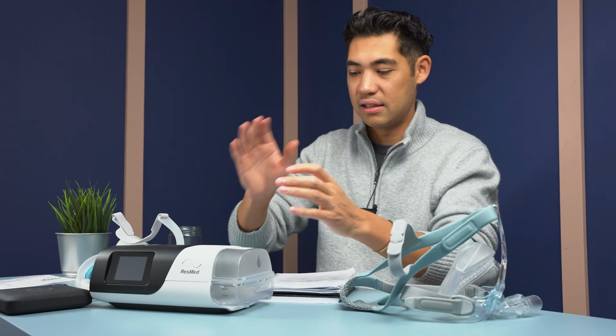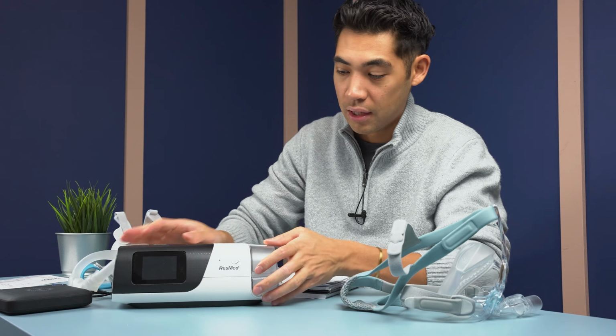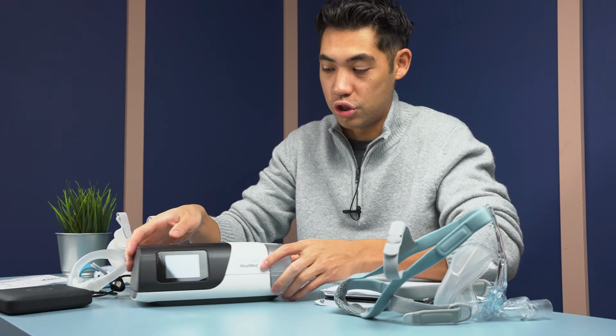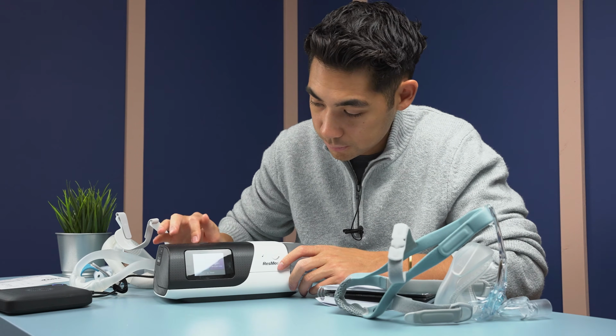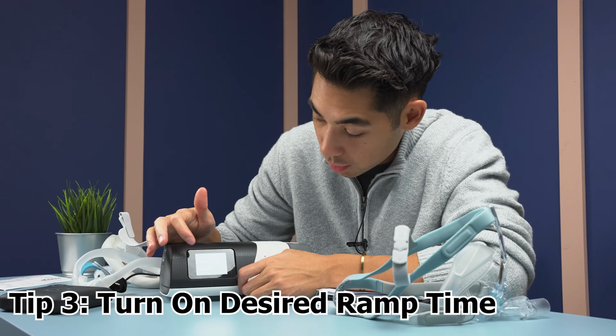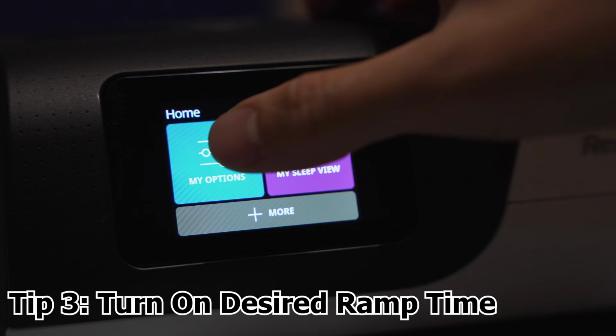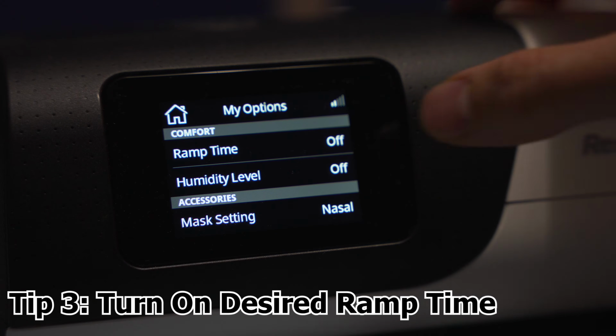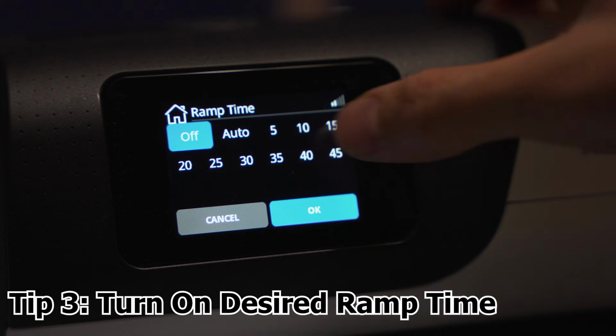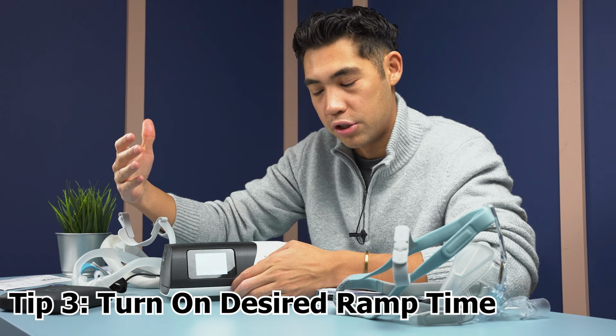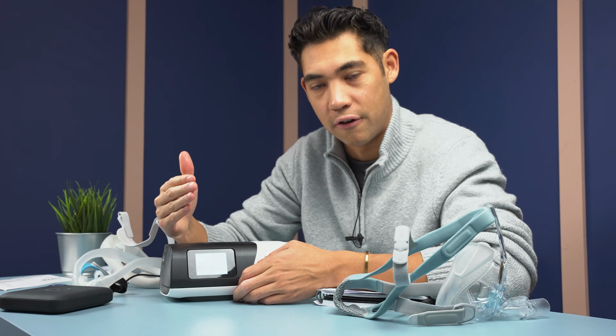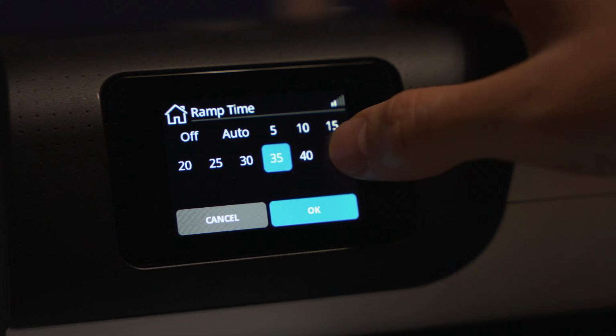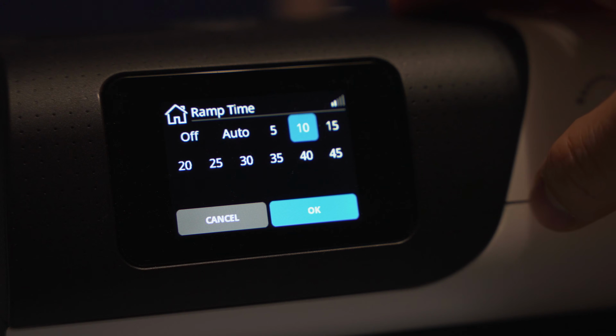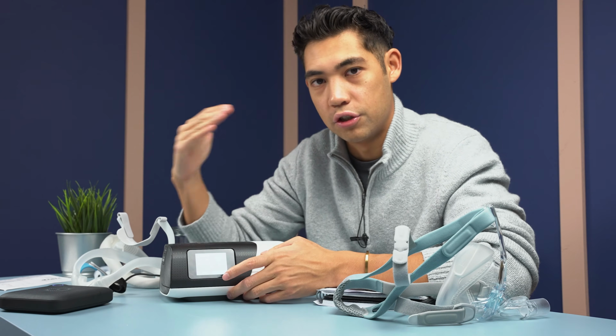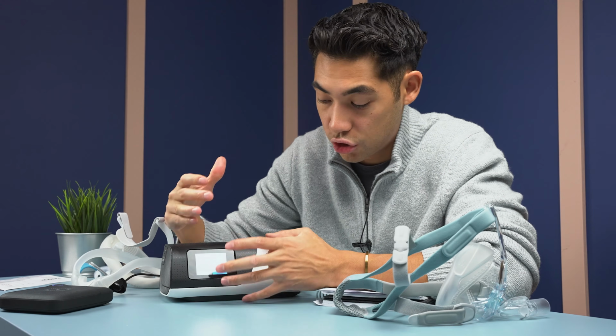Okay, the next thing is the CPAP machine settings itself. So there's a couple of different settings that we can change on the CPAP machine here. So basically we can go into my options and change any settings there. So for example, with ramp time, you can change the amount it ramps up to your prescribed pressure. So if your pressure is a 10, it's gonna start at 4. And then if you click say 10 minutes, right, it's gonna take 10 minutes for it to go from a 4 to a 10.